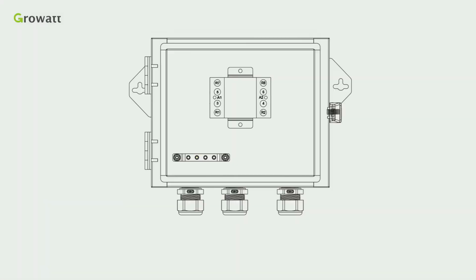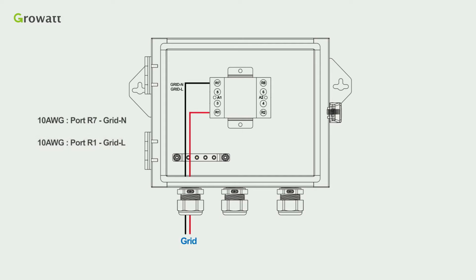Firstly, for grid connection, use the 10 AWG cables to connect the port R7 from the N line of the grid and connect the port R1 from L line of the grid. Use one 16 AWG cable to connect the port 3, port A1, and the other 16 AWG cable to connect the port 5, port A2. Connect the grounding cable finally.